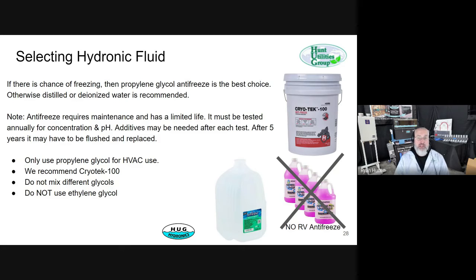The main thing is you want antifreeze that's rated for this job, for hydronic use. Cryotek-100 is what we sell, works very well. We recommend generally a 1-to-1 mix of the Cryotek-100. So 1 bucket of this, 1 bucket of water, and that gives the best protection and best performance for the price. If you're going to do a straight outside snow melt application, at least up around our neighborhood, you're going to need pretty much straight from the bucket. It's just a little bit of water added.